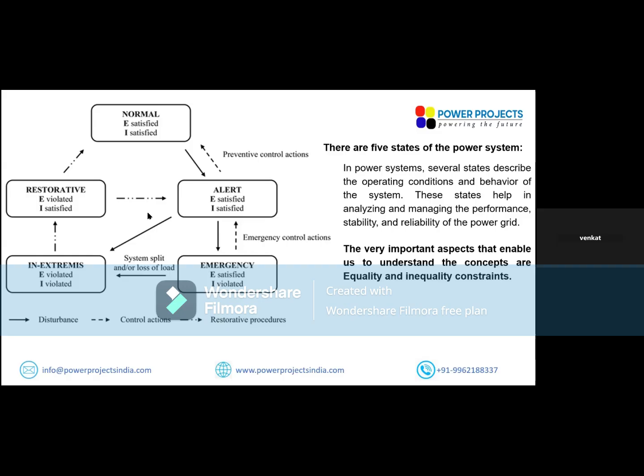Okay, then next is generator power output. So the next inequality is generator output limits. Each generator output must be within its operating range. I have already told you that rating is very important. So in generation, the most stringent constraint for any equipment in this power system is the generator. Even a transformer, you can load to its fullest for a few hours. You can load above it, 110% or 120%, but not for all 24 hours. You can load it for 1 or 2 hours, because once you remove the load, the transformer will come back to normal. It can operate at 110%, but the generator will operate only within its limit.